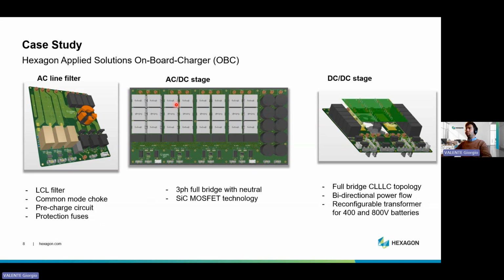We then have the AC to DC stage, which is basically a 3-phase full bridge converter with the neutral as well. Then we have the DC to DC stage, which is a fully bidirectional full bridge CLLC topology. It's essentially symmetrical, so it's fully bidirectional. We have a transformer that, depending on how you connect the winding, can give either 400 volts or 800 volts output, based on the batteries you have.